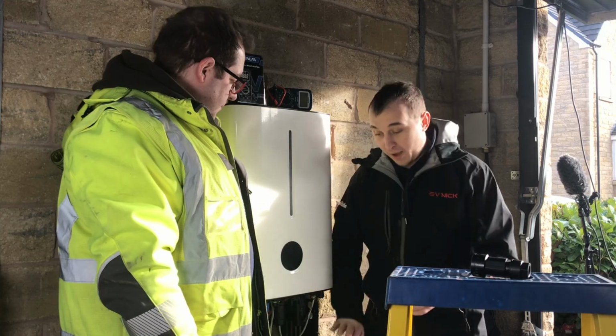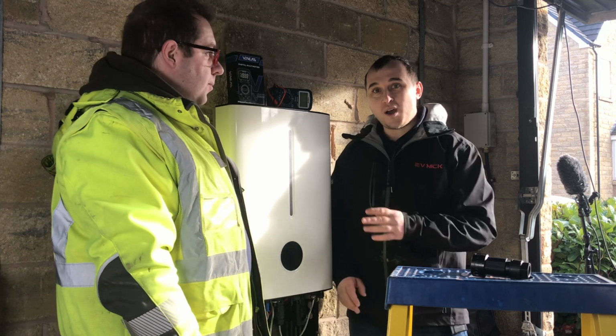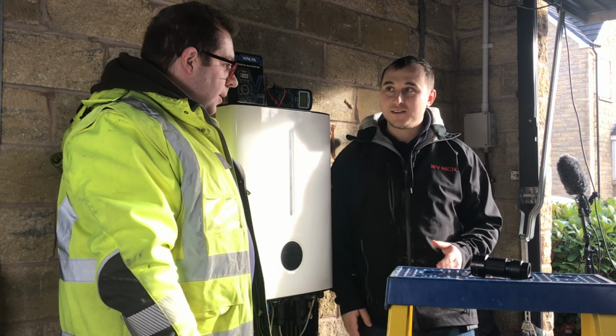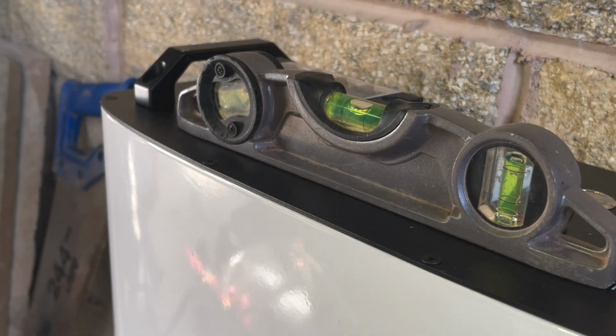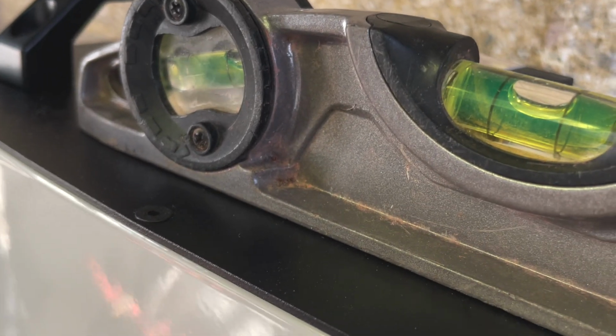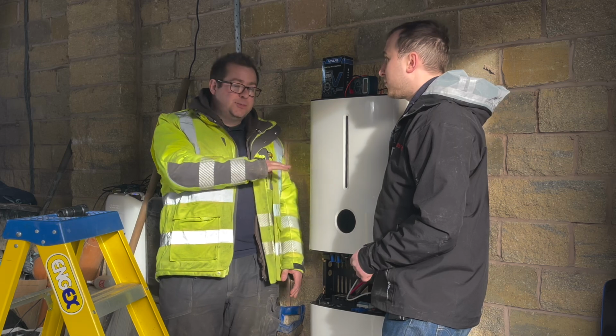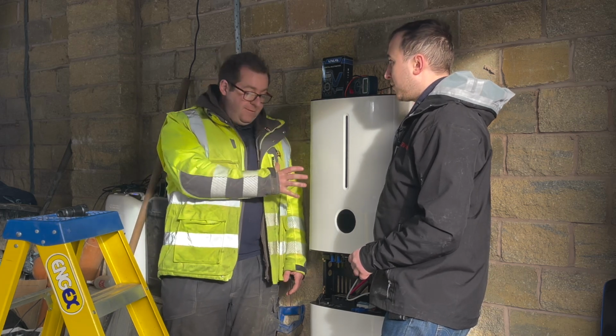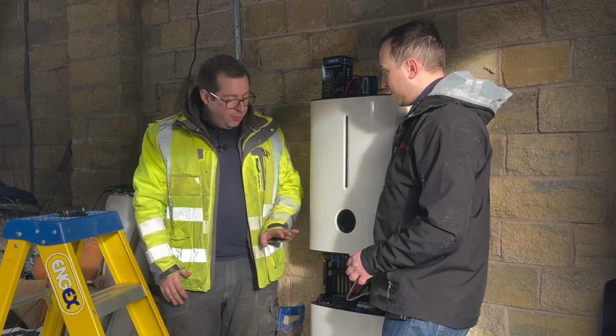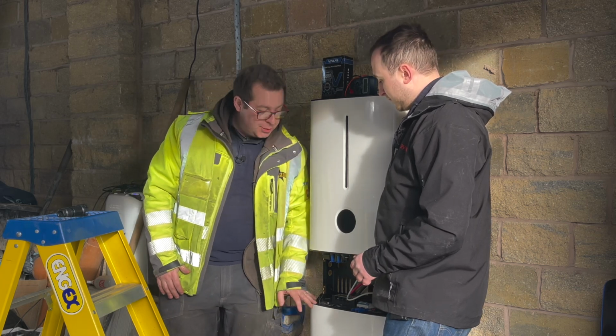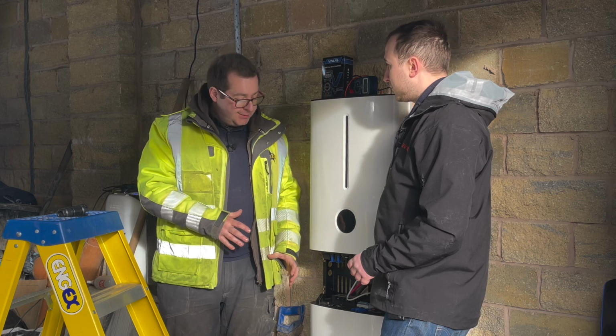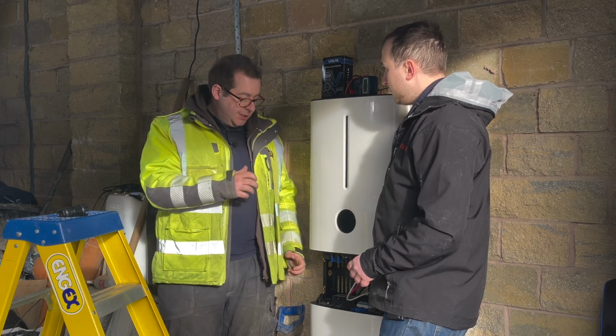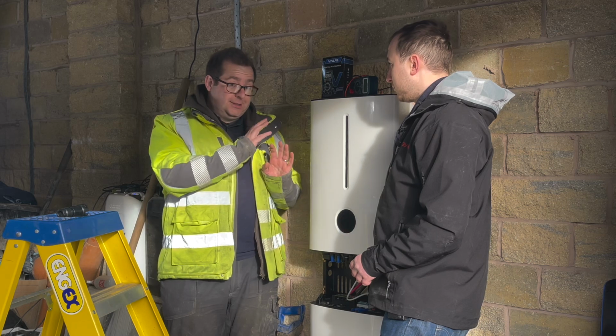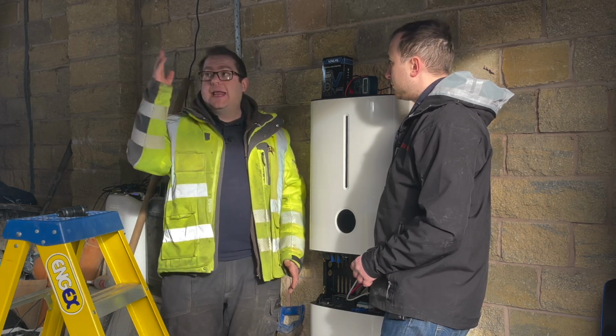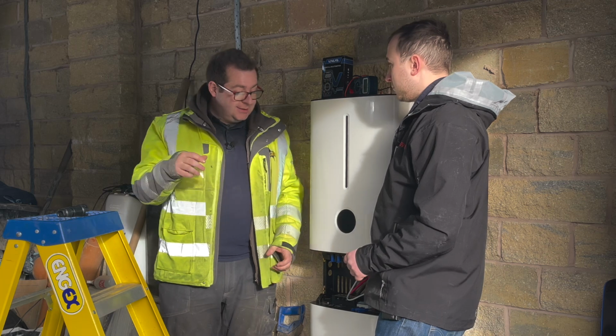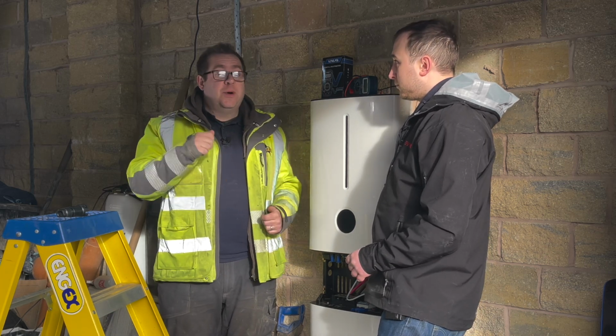So Lee, we've put the battery on and the inverter on first. Why have we put these on the wall before putting anything else in? Getting the battery on the wall so we can set the height, then build up the bracket system, which fits together nicely, gets all your spacing. Then we put the inverter on. That allows us to make all the connections safely between the battery and the inverter before it's energized. Establish all the connections, make sure we're happy with everything while it's completely dead, and then we can start working our way back to the consumer unit so that we can get it to a point where it can be energized and tested.